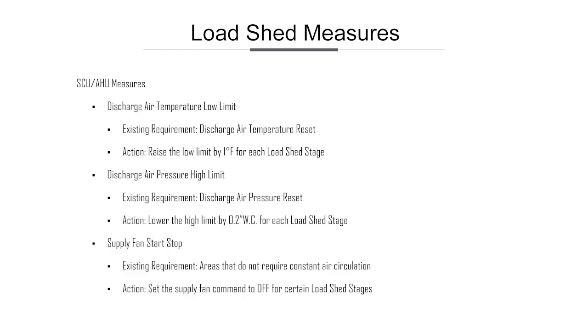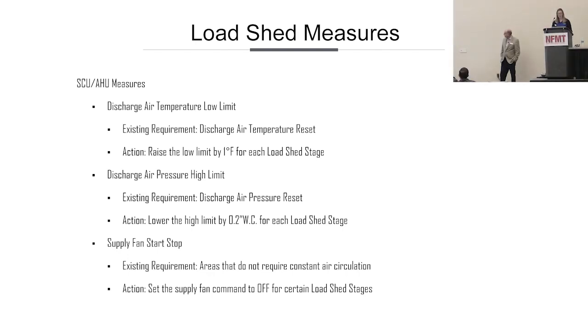For the SCUs or the air handlers, we did discharge air temperature low limit resets so that it was basically spreading out that band a little bit of what it was having to maintain. We did discharge air pressure high limit changes so that it was allowing for the fan to slow down and not have to ramp up as much as what it would in normal operation. And then, simple as it can be, just shut it off if you don't need it.